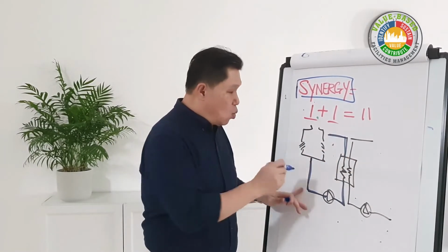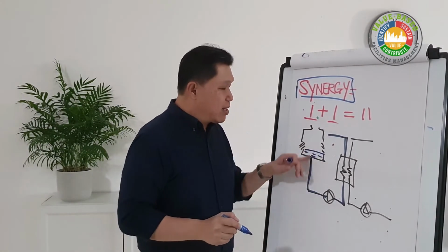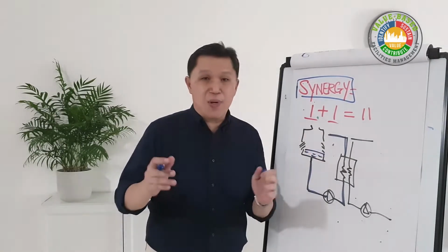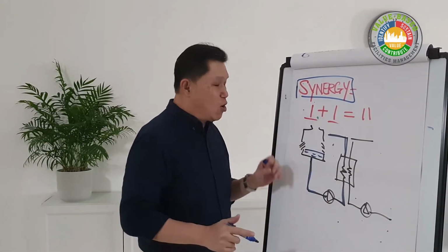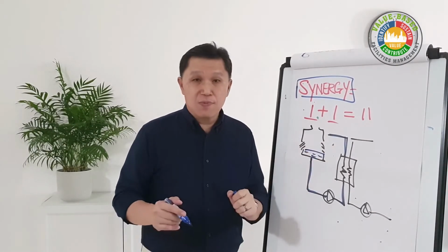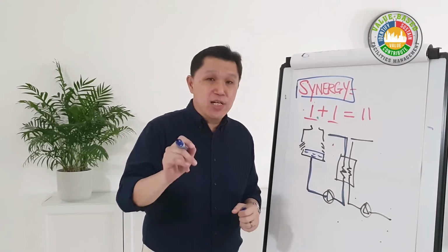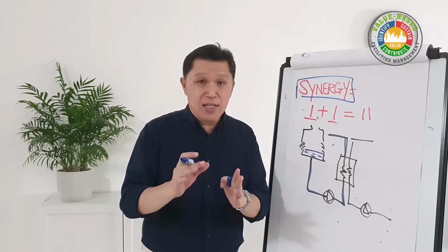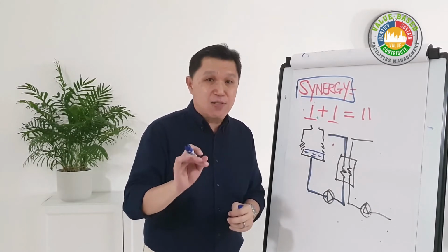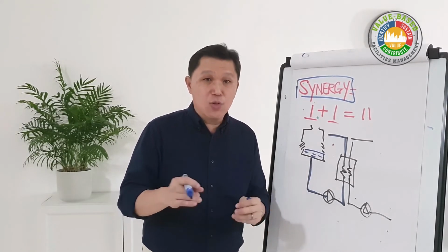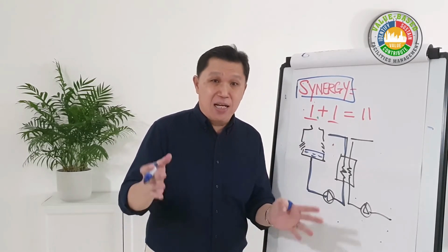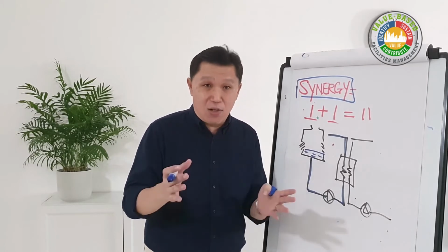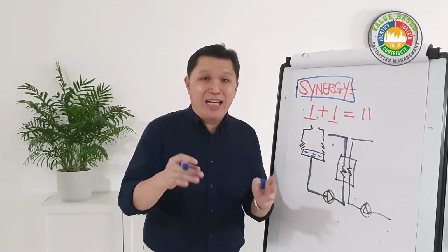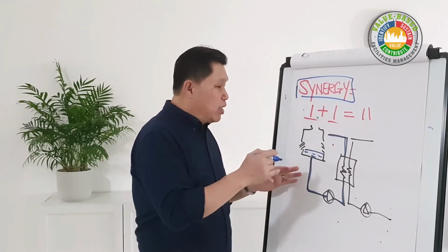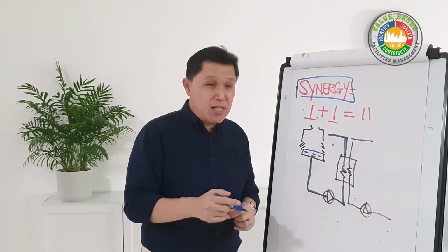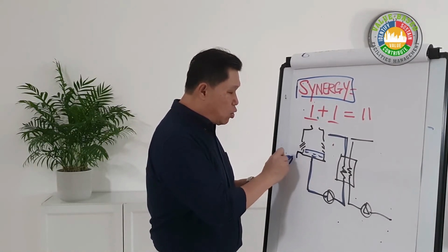Okay, let's talk about water. You know that the water inside this cooling system is based on an open system, whereby there will be evaporation and there will be drift loss. One way to ensure the efficiency of the heat exchanger is kept at its optimum is by having chemical treatment using corrosion inhibitor and biocide to prevent corrosion and to prevent scaling that may cause a reduction in the heat exchange.